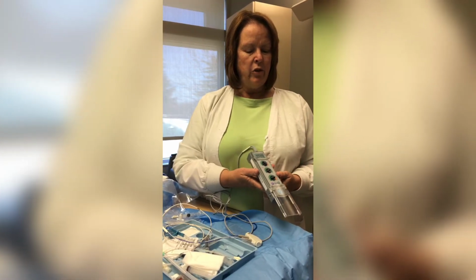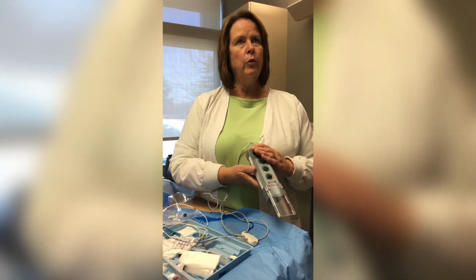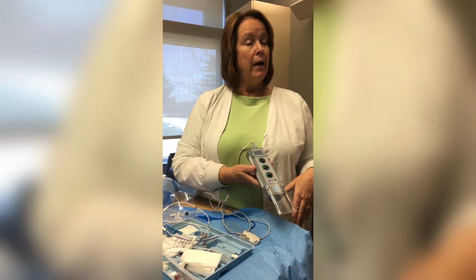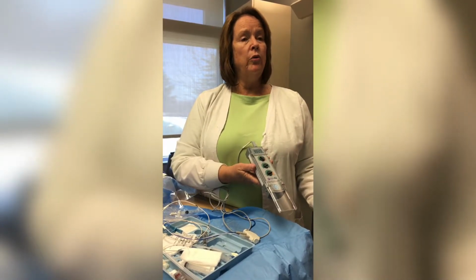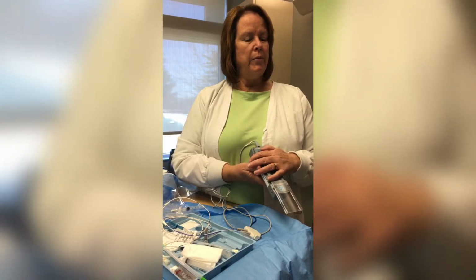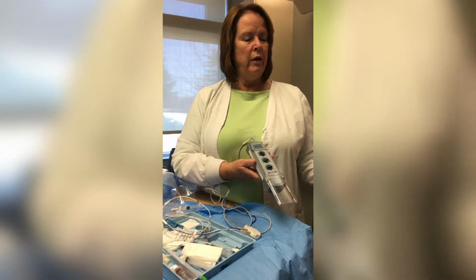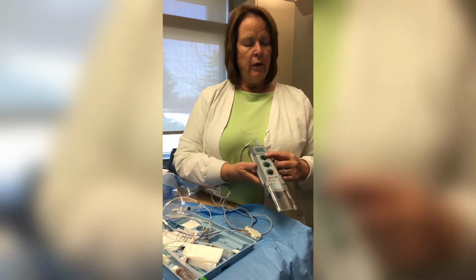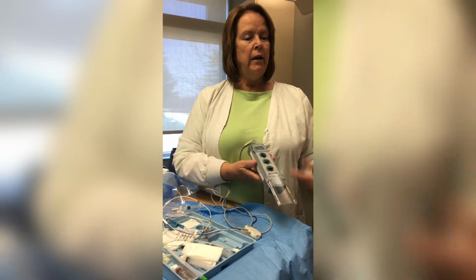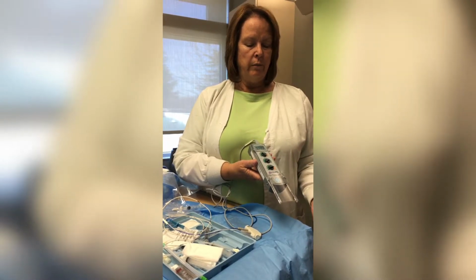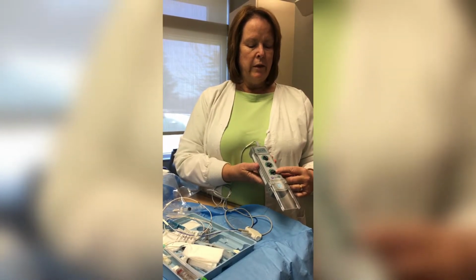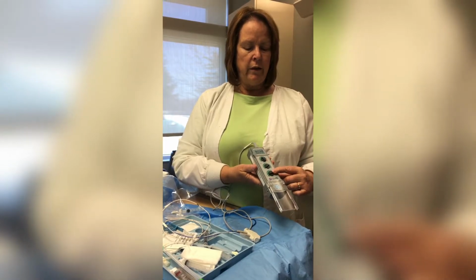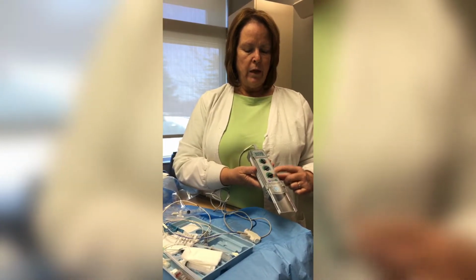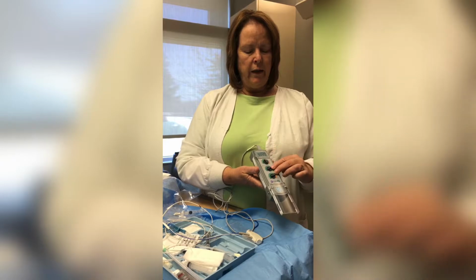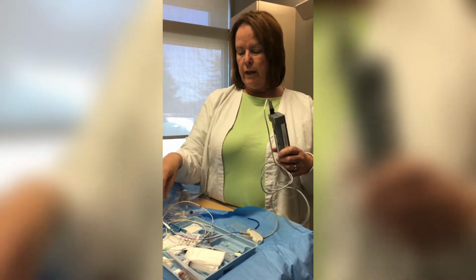You want to have it over here at the sensitive side when you start, just so you can sense the patient's own beat, because this pacemaker works by demand. If your patient has its own heartbeat, the pacemaker stops. If it doesn't have its heartbeat within the amount of time that is set on here, then it will give it a spike and cause the patient's heart to beat. So you want it to be sensitive to the patient's needs, and that is what the sensitivity is about.